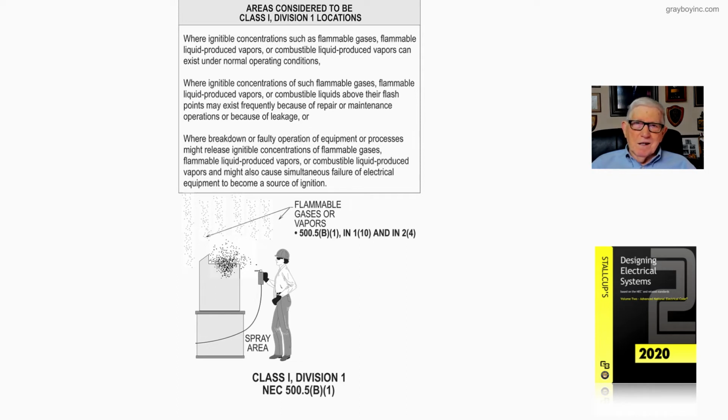But to get the classification and actually perform the classification, we would reference NFPA 497 and go through the chapter, and I believe it's chapters 4 and 5 mainly that you would look at. And you would review if the equipment is existing, what would be the conditions of classification, or if it was new equipment that you were installing.